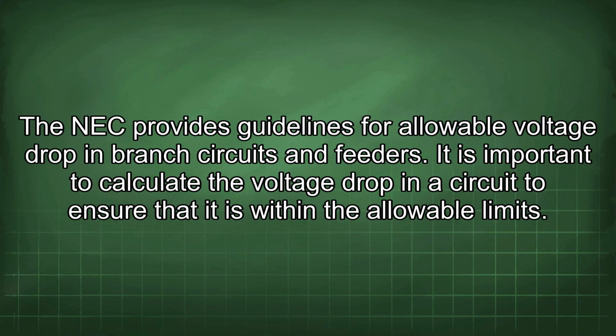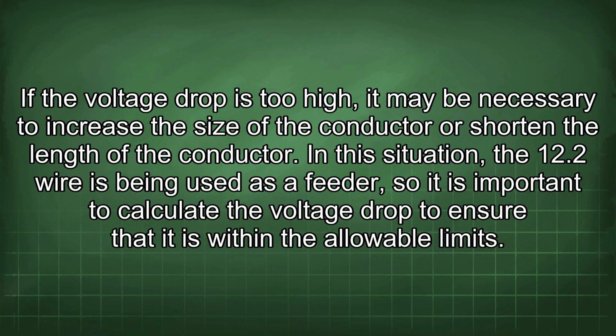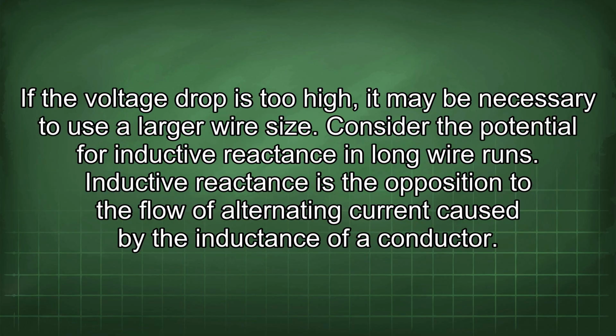The NEC provides guidelines for allowable voltage drop in branch circuits and feeders. It is important to calculate the voltage drop in a circuit to ensure that it is within the allowable limits. If the voltage drop is too high, it may be necessary to increase the size of the conductor or shorten the length of the conductor. In this situation, the 12.2 wire is being used as a feeder, so it is important to calculate the voltage drop to ensure that it is within the allowable limits. If the voltage drop is too high, it may be necessary to use a larger wire size.